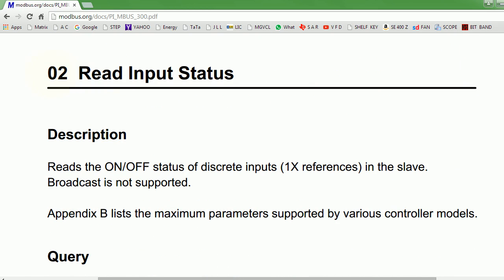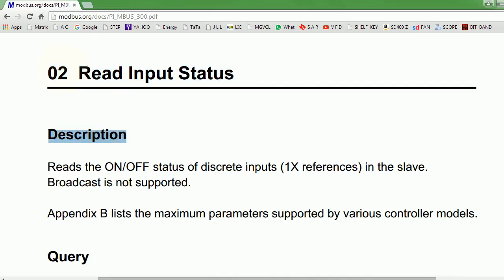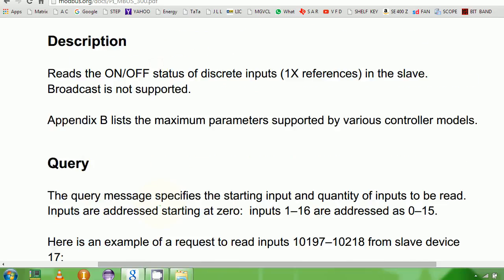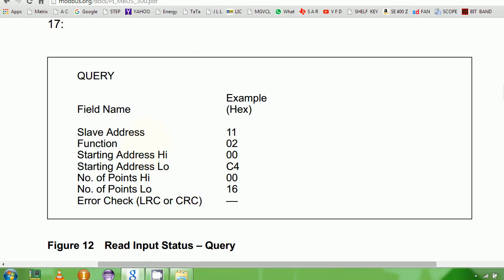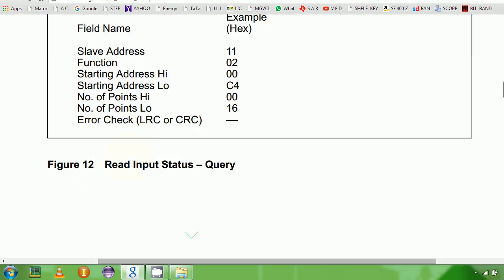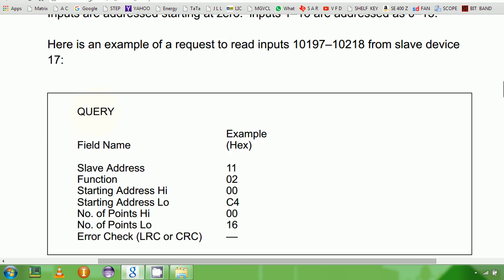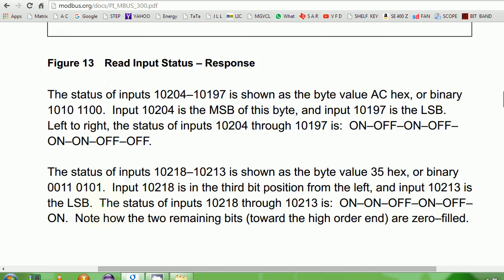Right now I'm just trying to see the functions and really have a bird's eye view at the Modbus document so that you get a little feel of what it really looks like. Function 02 is read input status. Input status is digital input bits — it could be a limit switch somewhere. You can't really write to it; you can really check whether input is on or off. It could be an A1, A2 contact of a contactor, and could be some single bit feedback. This is the query that you have to send to accomplish that, and this is the kind of response you'll expect from the device.